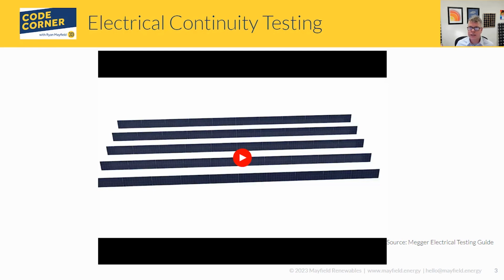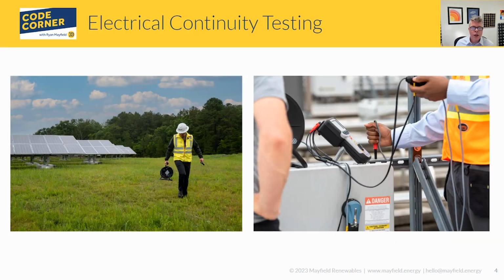These are tests that should be done regularly: at commissioning, making sure that everything's bonded together properly, and then as part of your maintenance protocol. You can see here some still pictures from the field. You have a long test lead on the left, and the tool being used on the right. These tools are great for verifying this grounding and bonding.